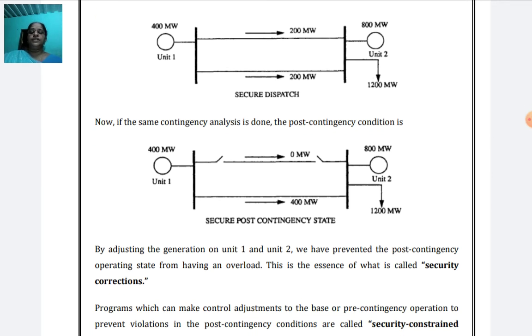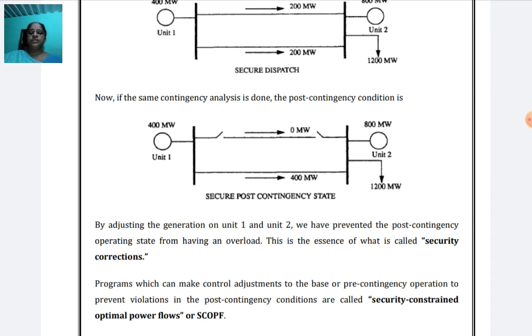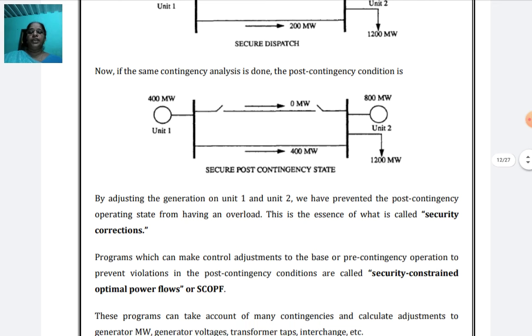Then the secure post contingency state. In this state, we are adjusting the generation on unit 1 and unit 2, that is 400 and 800. And then the line 1 outage happens. Line 2 only carries the 400 megawatts from unit 1. But line 2 is not overloaded, because we have taken corrective actions. So this is the secure post contingency state only. Here we have to do the security correction. What security correction are we taking? Adjusting the generation on unit 1 and 2. This is the security correction. Therefore this state is the secure post contingency state.